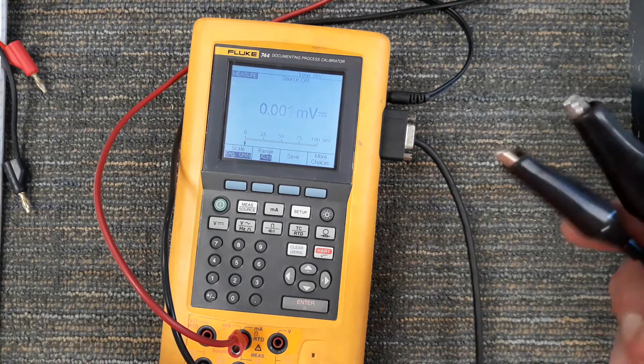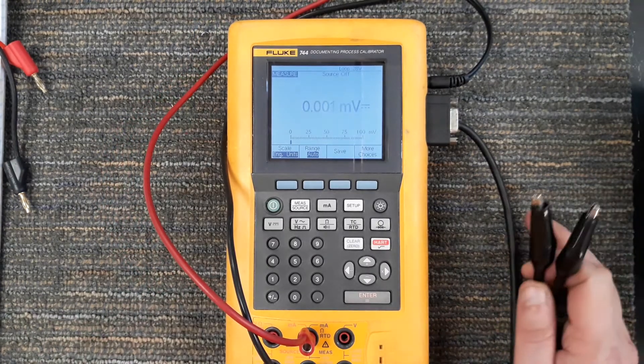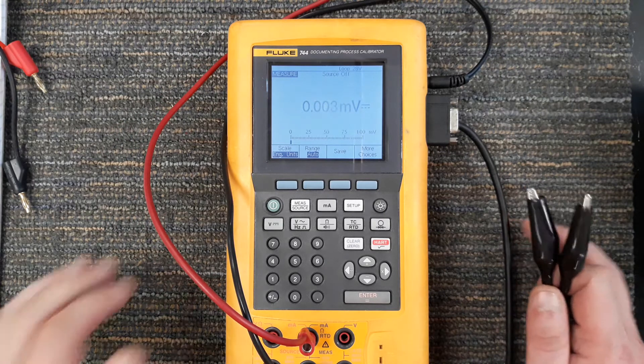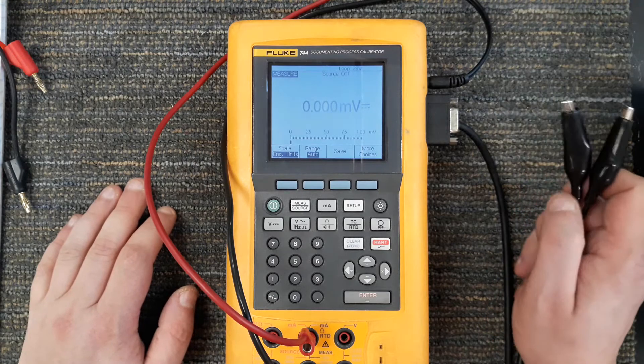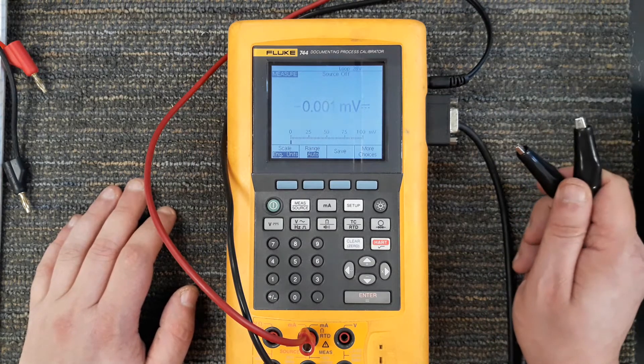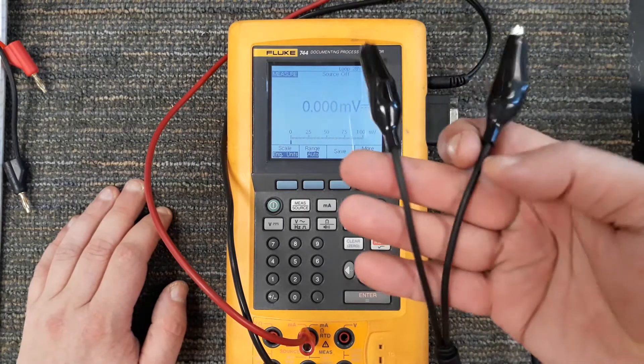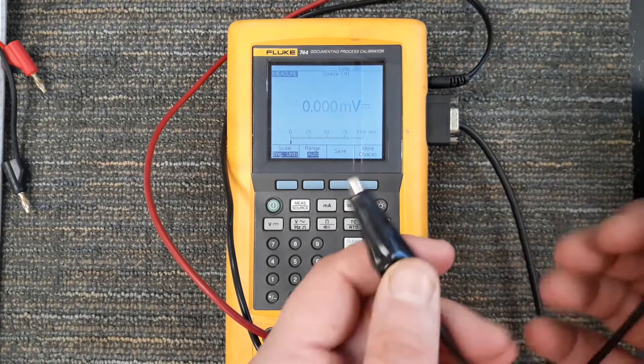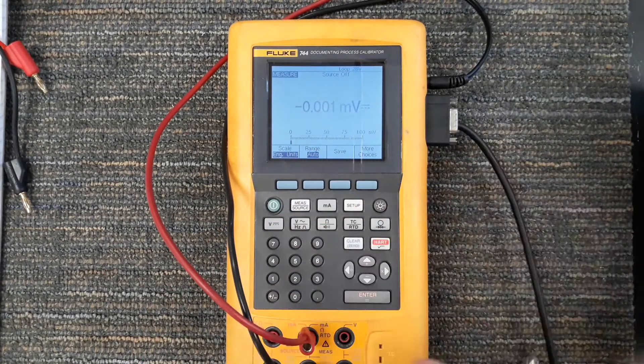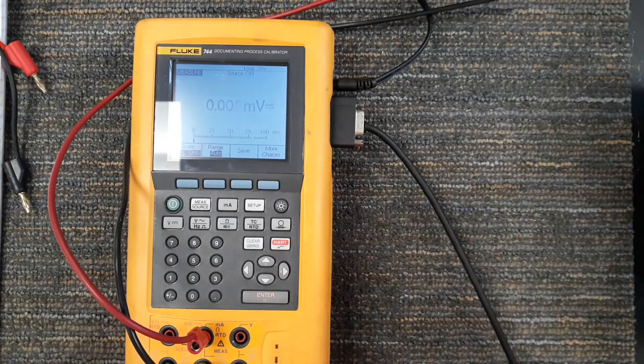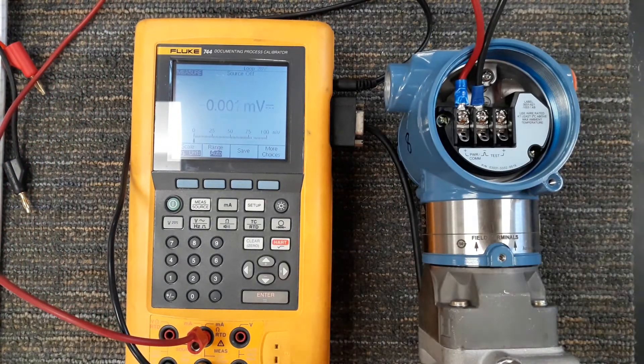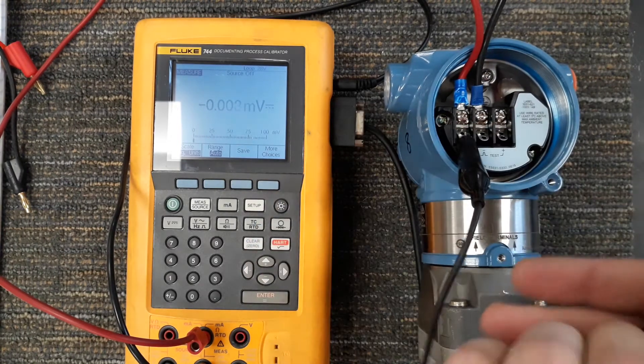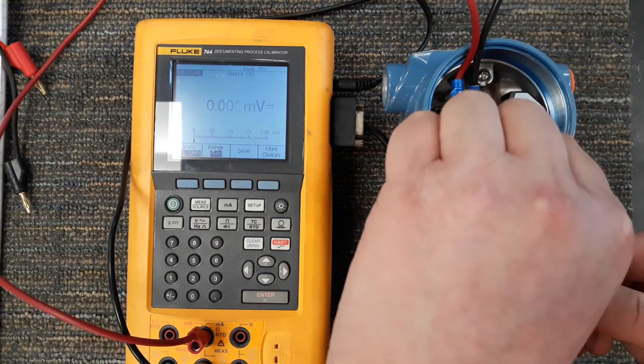Now communicators, even though if you pull out another communicator like the Emerson 475, it has a red lead and a black lead, but to communicate polarity is not required. As you see, they're both black wires. It doesn't matter which one I connect to positive or negative. I'm just going to connect this one to positive and this one to negative.